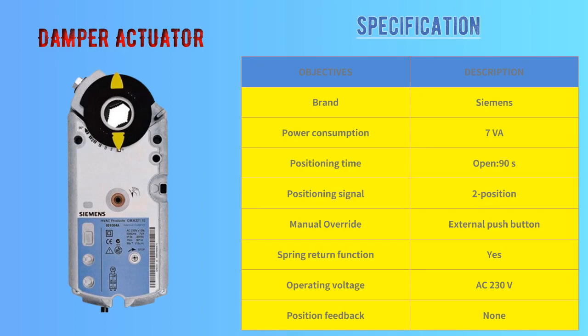Fourth, this is also a damper actuator from Siemens, but there is a minor difference. As you can see, it is written 2-point, meaning only 230 volt AC power is applied to it. That means this damper actuator is used as a fire damper actuator. The major point is it has a spring return function, meaning when any emergency happens, it will close the damper immediately.